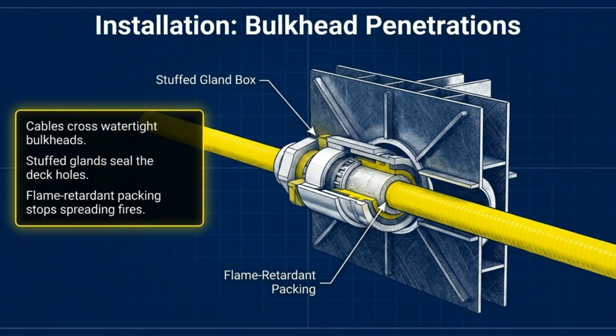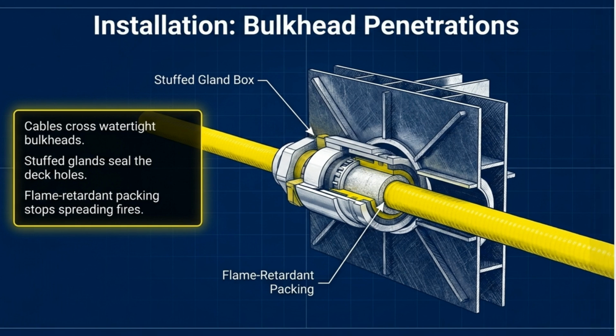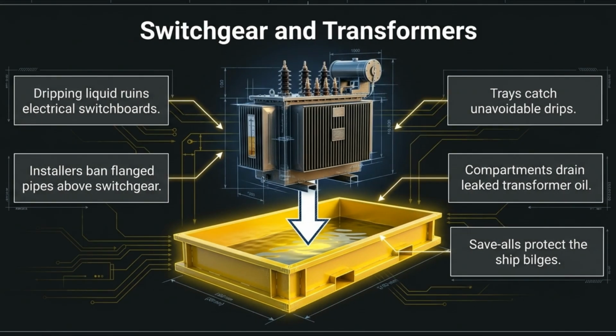When cables pass through watertight bulkheads, they use stuffed glands. These include flame-retardant packing to maintain the integrity of the bulkhead and prevent the spread of fire. Switchgear and transformers are vulnerable to leaks. To keep them safe, installation rules forbid flanged pipes above them and use drip trays to protect the ship's bilges.